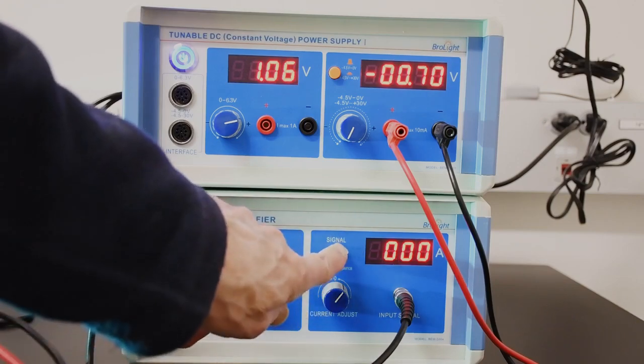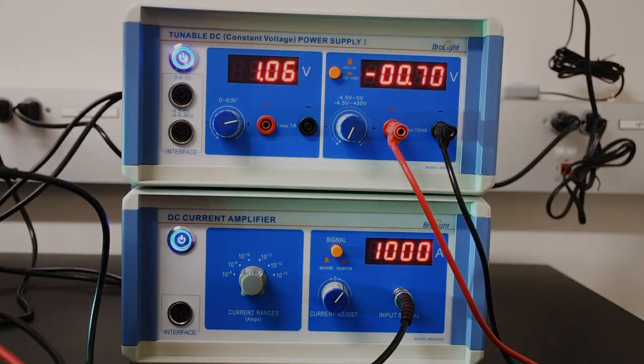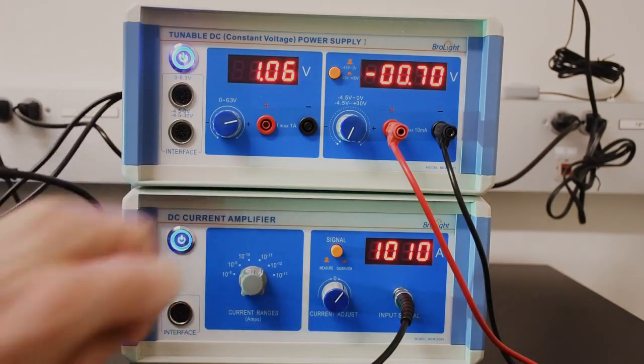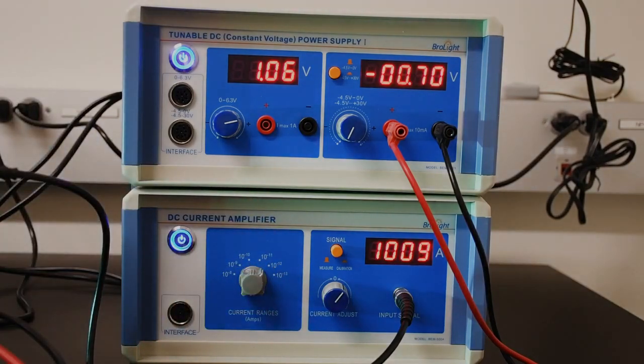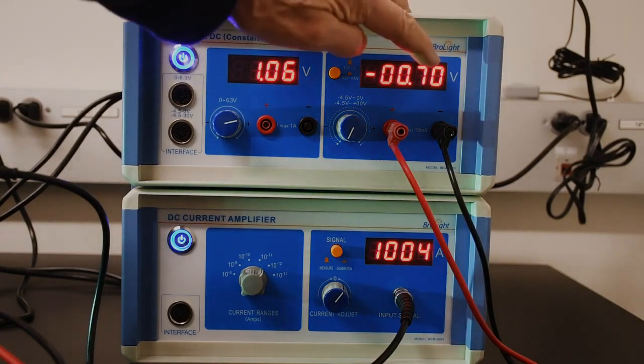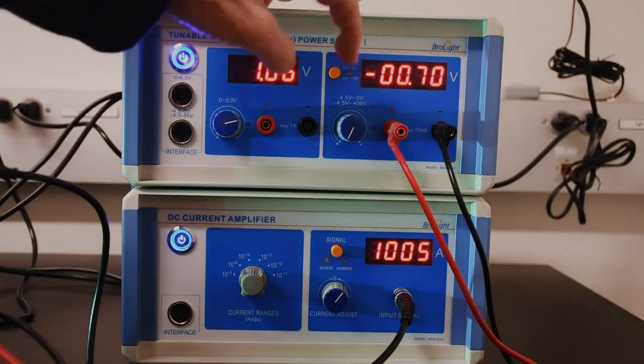I'm going to check the zero point here, and we don't have any current. Then looking at the signal, we have 1014, and the scale here is 10 to the minus 12 amps, so it's around 1009, 1008. It'll vary a little due to noise and changes in the photodiode's response, but it's right around 1000 picoamperes at the moment. The voltage applied to the photodiode is only 0.7 volts.